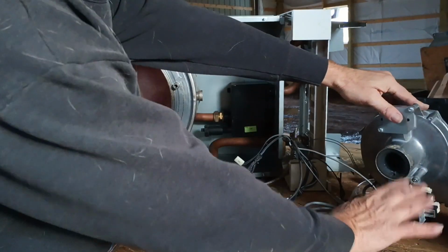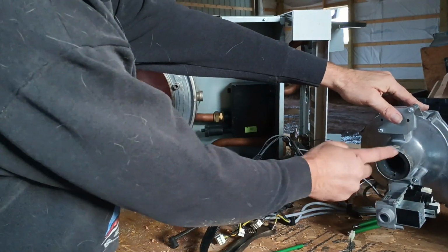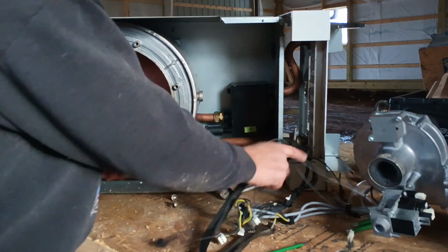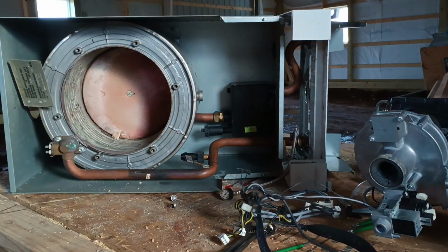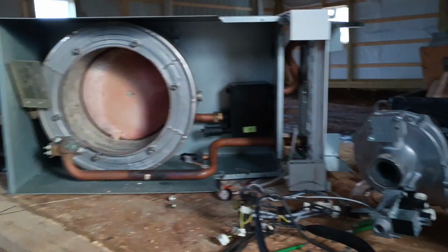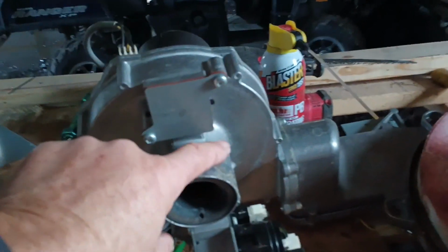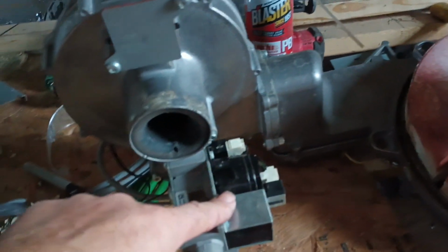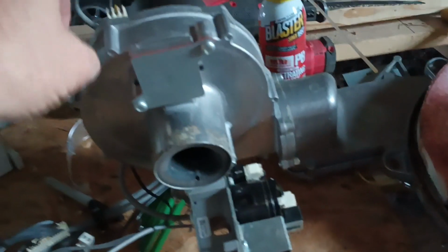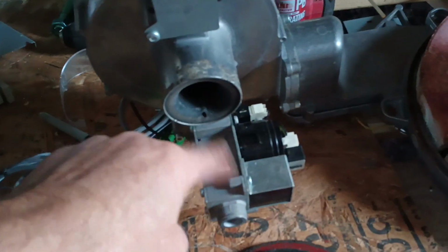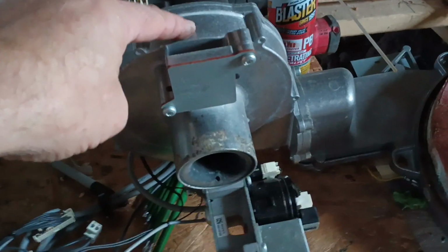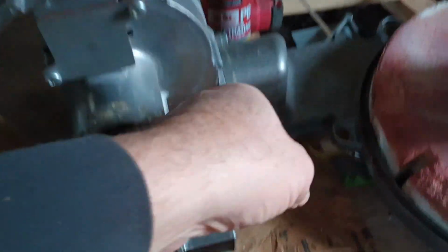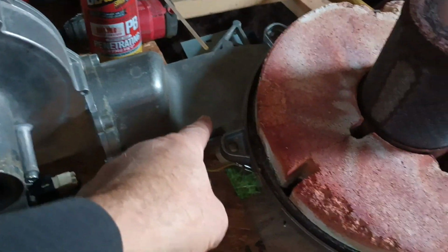Gas valve. This is the venturi, the air intake for the primary air. Get the camera off the stand. So venturi, primary air, gas valve. It's a negative pressure valve. When the vent motor starts up, it'll slurp the gas in at the firing rate that it needs, mix the primary air with the fuel. Up the air fuel duct comes in on the back side of the burner.